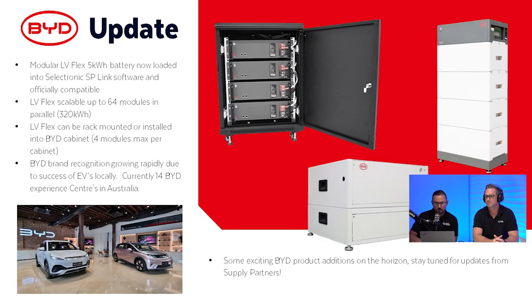Looking at the BYD front, we're seeing a lot of popularity with the low voltage Flex 5 kWh modular battery. This was recently made officially compatible with the 48 volt SP Pro inverters, and you'll now find them in the SP Link software. They're scalable up to 64 modules in parallel to deliver up to 320 kWh of storage. They can be rack mounted, or installed into the BYD Flex cabinet you see at the top left.